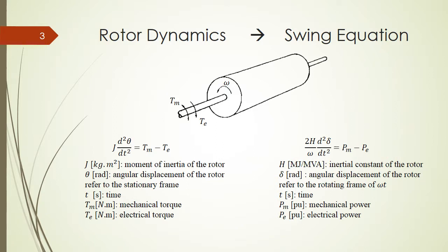We also express the same relations, but here we have H as the inertial constant of the rotor, which is megajoule over megaVA. This one expresses the relation between the kinetic energy of the machine or the rotor in comparison with the base power of the system. The P_m and P_e is the power that applies to the rotor, which is also in per unit. Delta here is the angular displacement of the rotor, but this time it refers to the rotating frame of omega times t. T here is also time. So we call this the swing equation, and this swing equation will be used to analyze the behavior of the rotor of the electric machine.